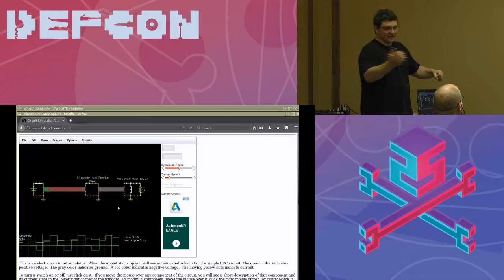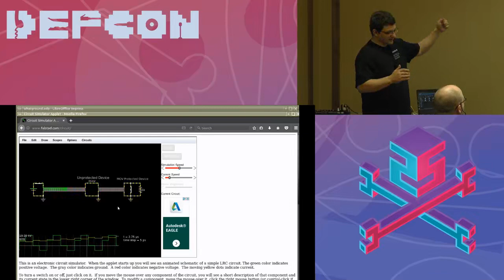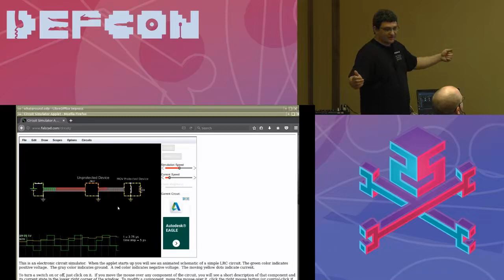But the bottom line is you just want to have protection on every important device. Things like motors generally, you might blow a hole in their insulation, but they can tolerate a lot more than electronics generally. So just ideally have protection at your panel, protection at your device, at any important device, and that's the best you can do. Any other questions?